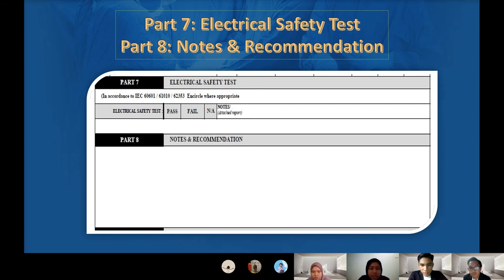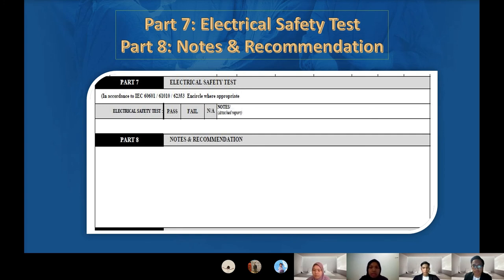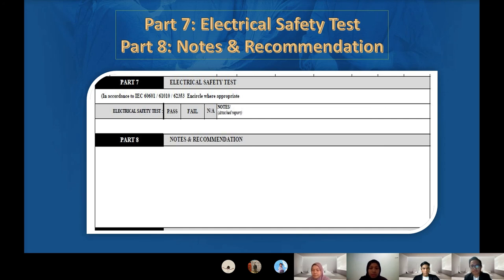For part seven, electrical safety test: this helps to prevent hazards and is important to ensure that the patient and staff are safe while using the equipment. For the safety analyzer, we use a Fluke model, and the results of the test will be attached in the attachment section. For part eight, notes and recommendations: the engineer will note down if the equipment has any damage or fault. For example, if the battery on the equipment is damaged, the engineer will note that the battery needs to be replaced.